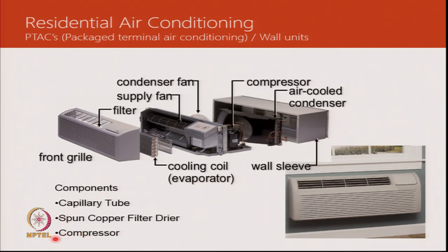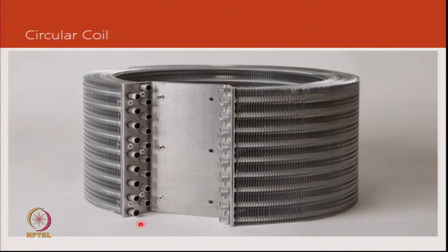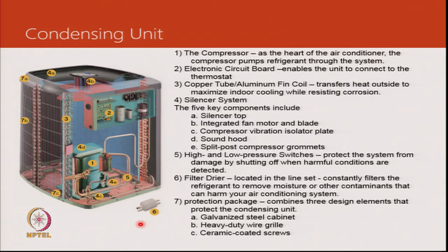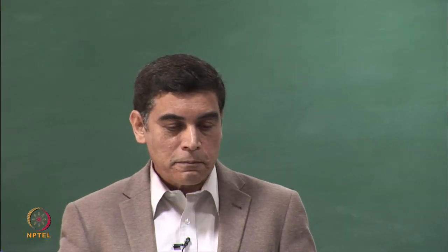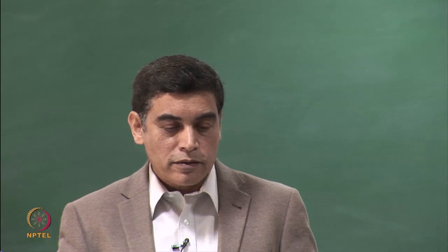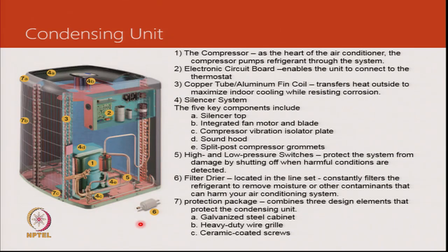So we have looked at capillary before, and then there would be a filter dryer to ensure that the capillary does not get choked, and compressor selection we have handled before. Then when looking at compact heat exchangers, for condensers typically it is common to use circular designs like this, or U-shaped designs. And then this gets into a condensing unit. So from a condenser we migrate to looking at a full condensing unit, where we have the compressor that we earlier looked at, how we selected it based on the ambient and the evaporating temperatures, and then we want to look at the control components that we need to integrate with that.